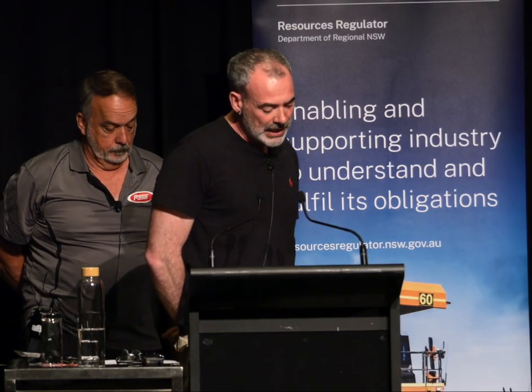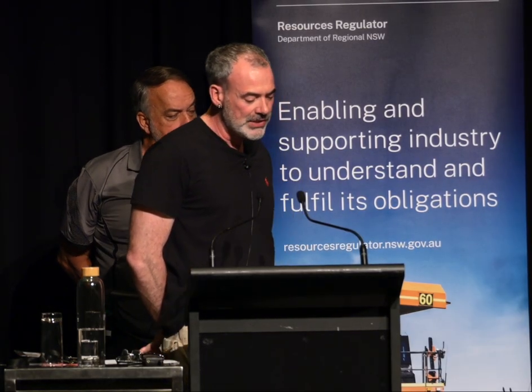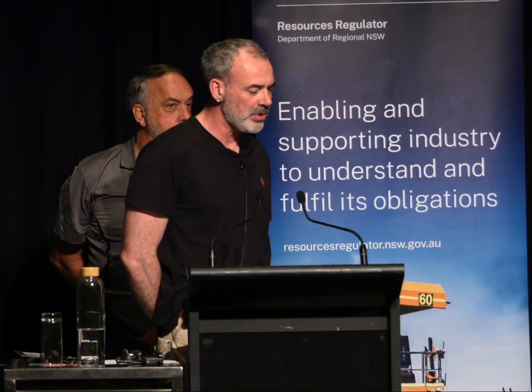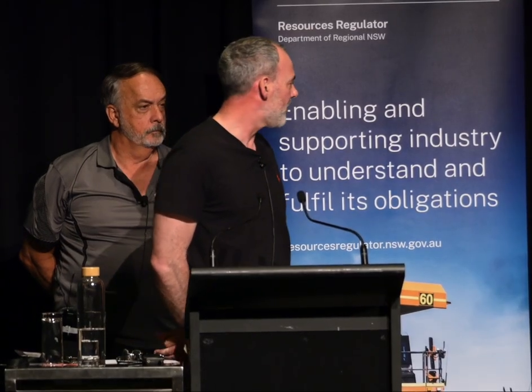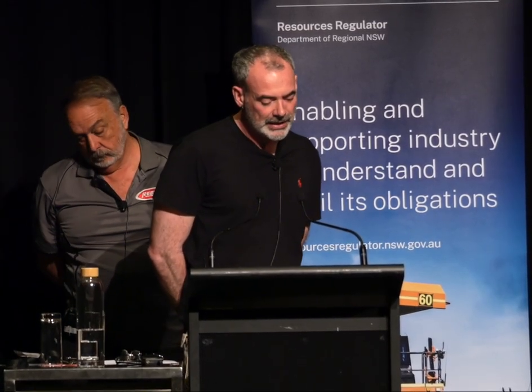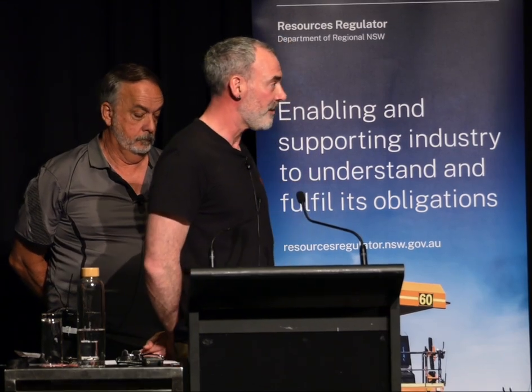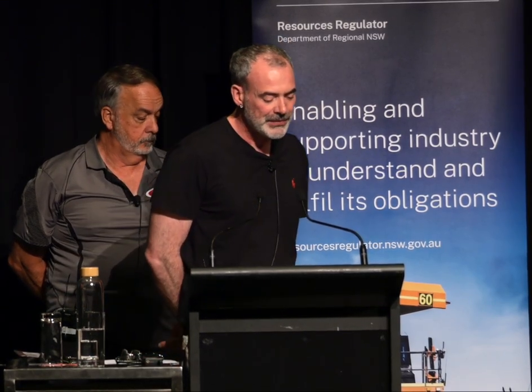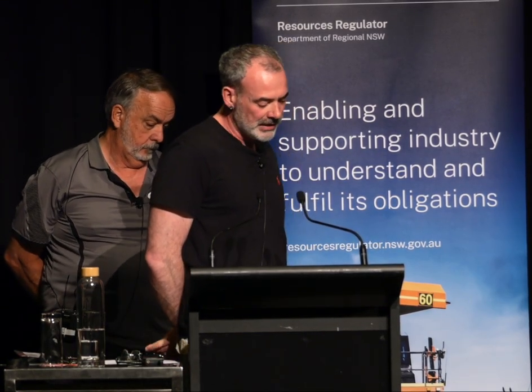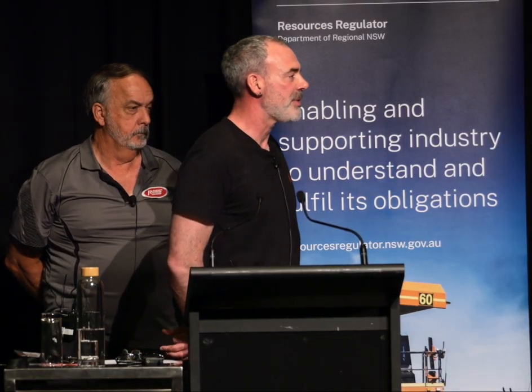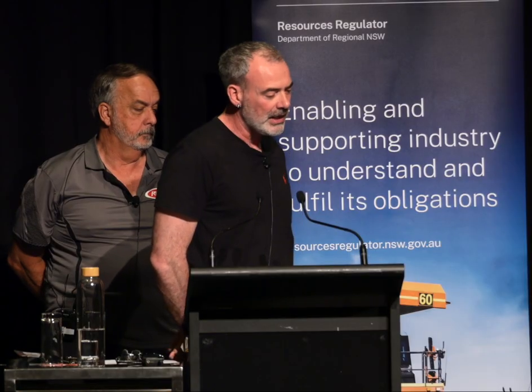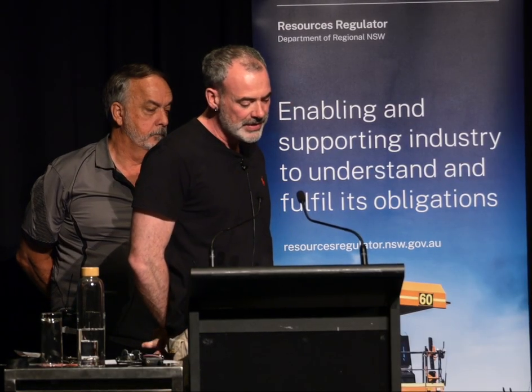So about the voltage class, where the primary voltage is less than 69 kV, there's plenty of retrofilling experience globally, and we think the transformer's dielectric design for mineral oil should be sufficient. Where the primary is above 69 kV, we think there might be a requirement for verification of the leads in the winding assembly, and we can assist you with that if necessary.